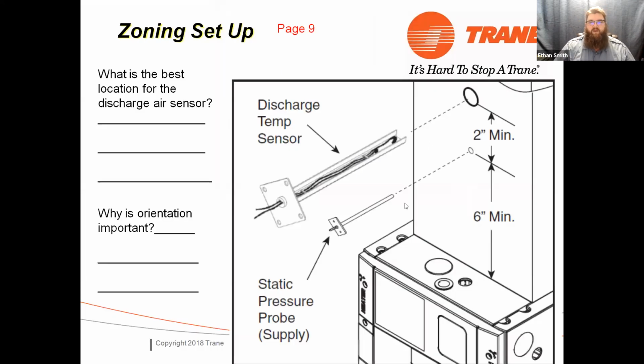Okay. When we're talking about where to put these things, guys, they want your pitot tube for your supply static a minimum of 6 inches off the top of the air handler. I would tell you to go as far as you can. You do want to be located in the ductwork as close to the center of the ductwork as you can be. That eliminates turbulence. And then we want our discharge sensor at least 2 inches away from the static pressure sensor.